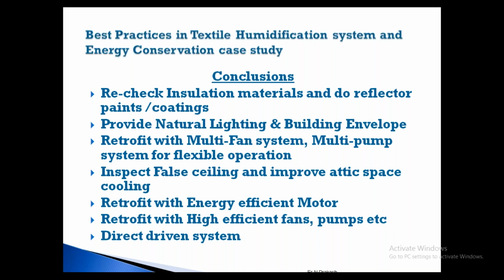Delivery and distribution losses occur immediately in the plenum itself. It will be exposed to direct sun, and the wall will be just cement plastered. Almost 8 hours in the daytime, the sun will be falling on that wall of the plenum, so whatever humidification you achieve becomes waste. So at that place, see whether it is possible to put in insulation, or plaster it with some thermocol insulation, or apply a reflector paint.